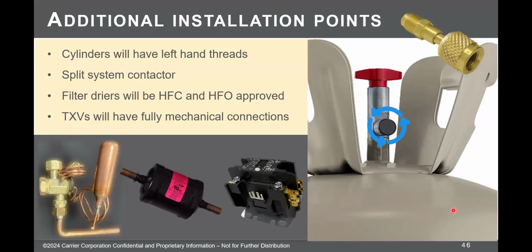Just to keep things moving, left-hand threads I mentioned. The filter dryers that come with the residential condensing units have straight connections on them now. It's the same technology in the filter dryers we had for 410A. In fact, two weeks ago, Mark Wiseman and I sat there and looked them up just to see, and it's the same manufacturer, same specs. It's just whether the connections are swedged or whether they're straight on there.